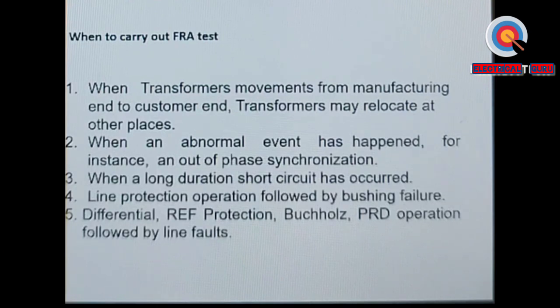Another case is line protection operations followed by bushing failures. Sometimes we have a fault on the transmission line and the line trips, but at the same time the bushing also suffers some failure and bushing blasting happens. Then there are differential, Buchholz and PRD operations followed by line faults. This is another condition where you say there is a fault within the transformer protection zone. It trips on transformer differential, followed by a line fault. Of course, these types of conditions are very rare and do not happen on a regular basis, but once in a blue moon this can happen.